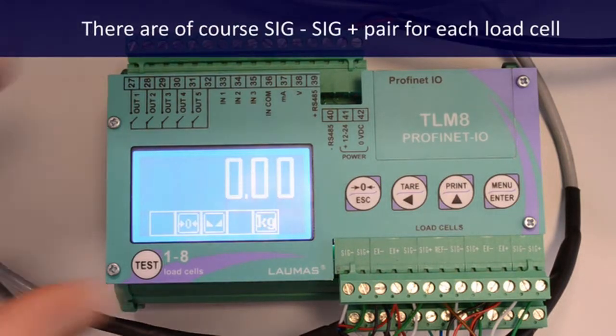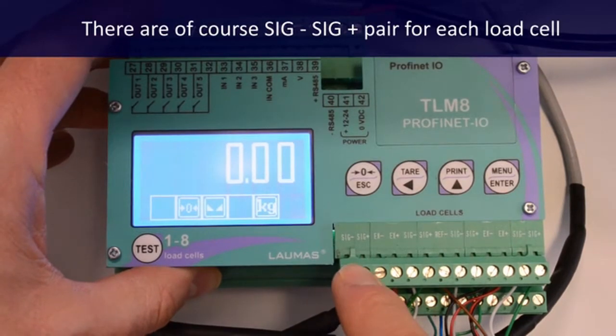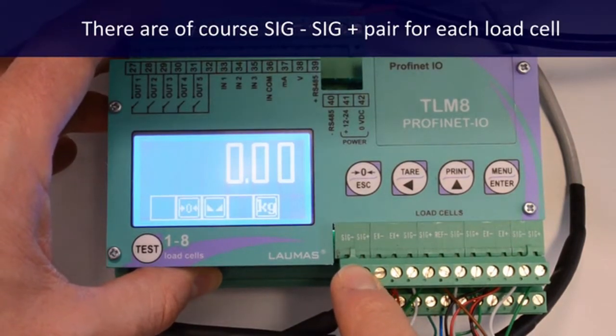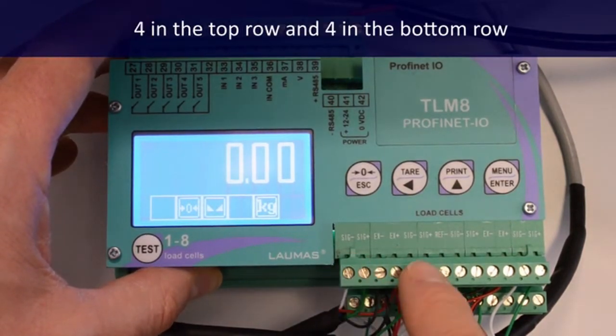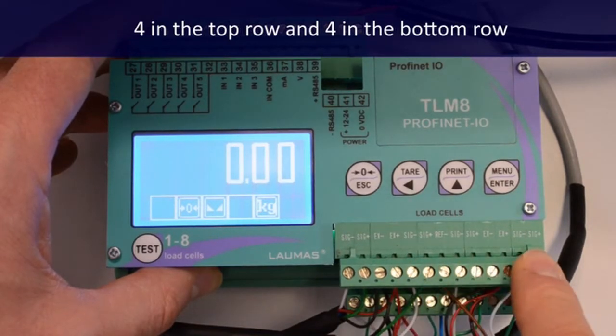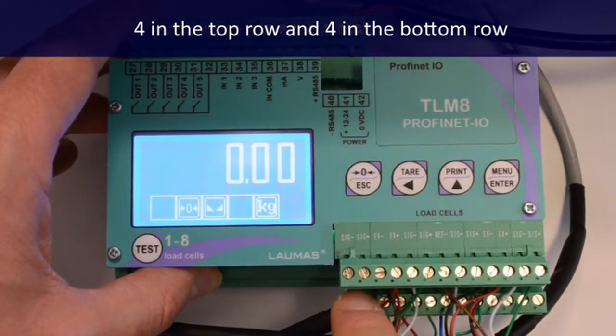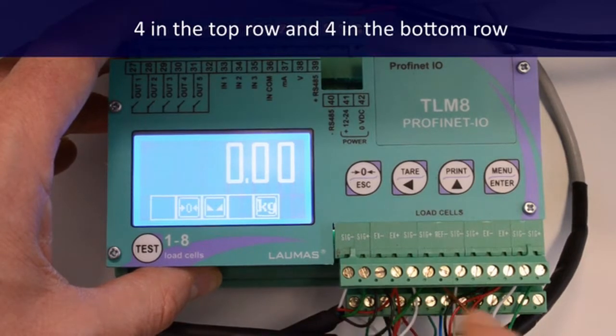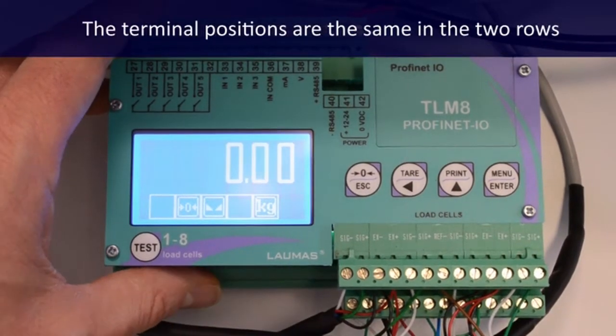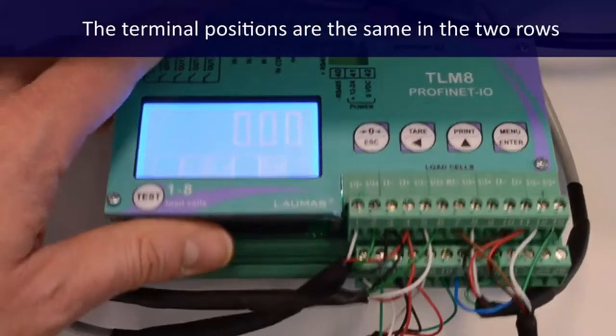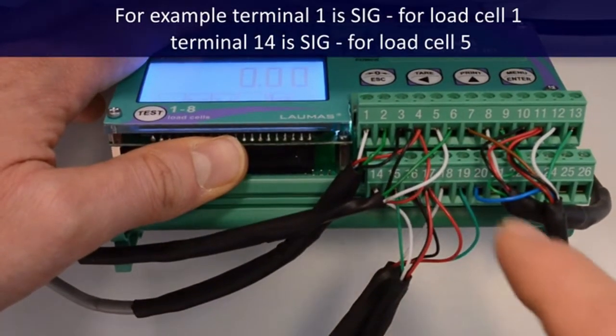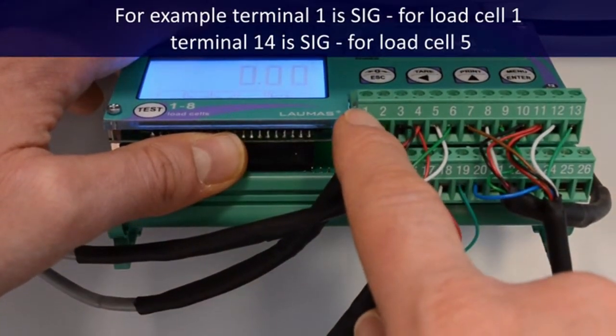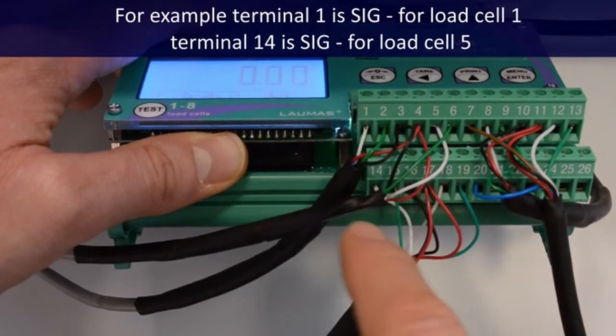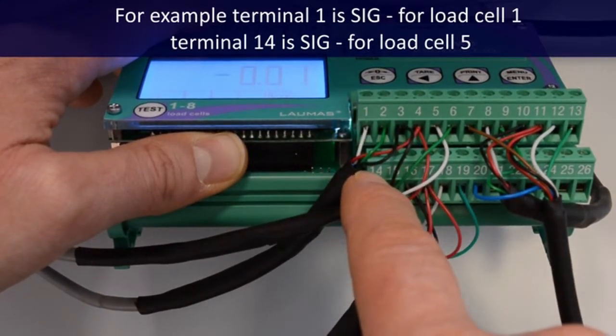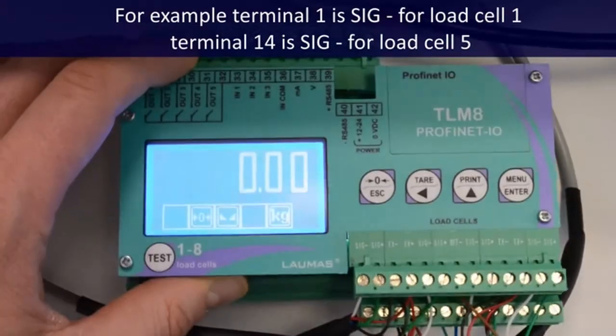There are of course a sig- sig+ pair for each load cell, 4 in the top row and 4 in the bottom row. The terminal positions are the same in the 2 rows. For example, terminal 1 is sig- for load cell 1. Terminal 14 is sig- for load cell 5.